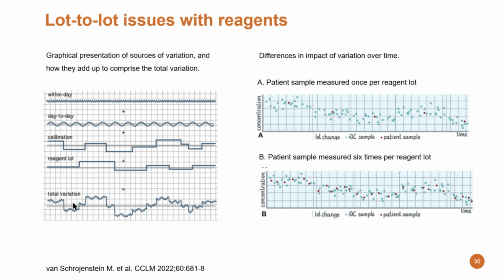On the right side, it's interesting to see the behavior of a QC material and a patient sample while you do lot changes. Also here on the y-axis, the concentration, on the x-axis, the time, and you see the dotted line here, that's the lot change, another lot change, another lot change, and here the fourth lot change. And you see that the QC, that's the blue ones, show clearly that there is a difference from lot to lot. If you just check with your patient material, and this is always the same patient, you see it behaves the same or similar. If you measure more patient samples, or measure patient samples more often, you can use this also as a type of additional quality control check.